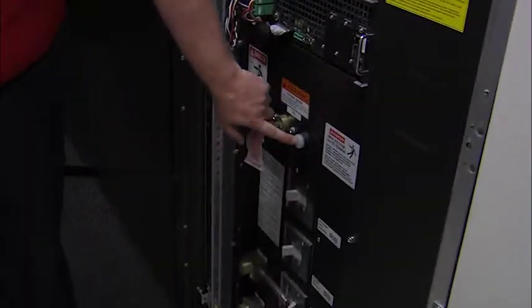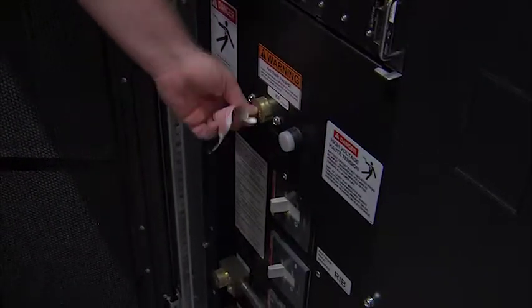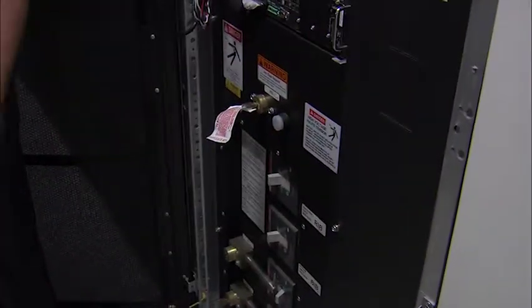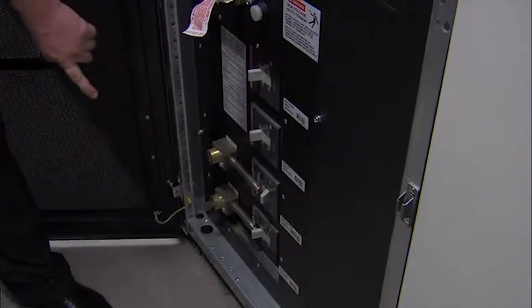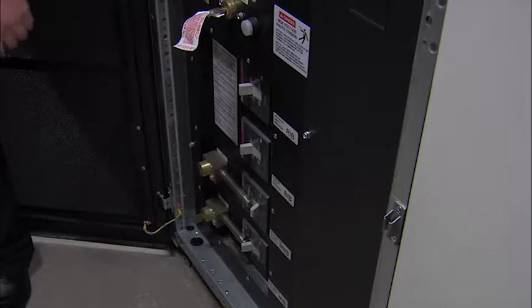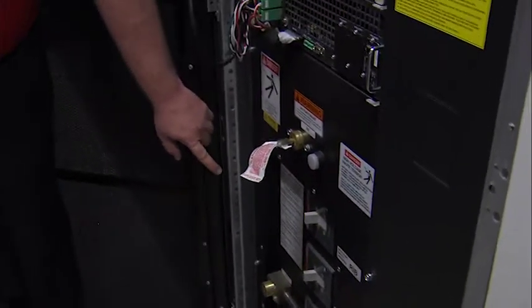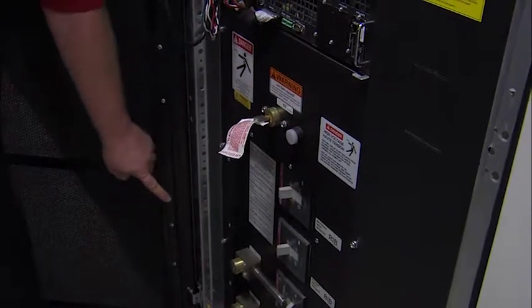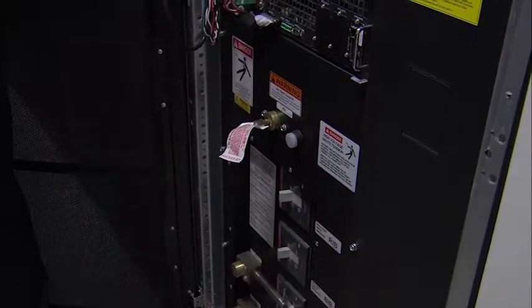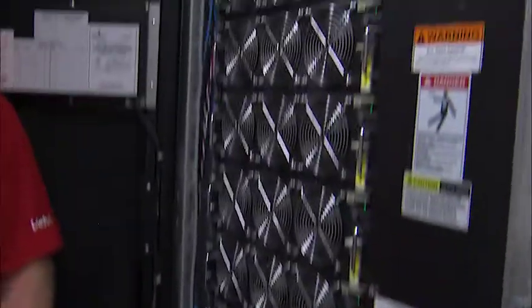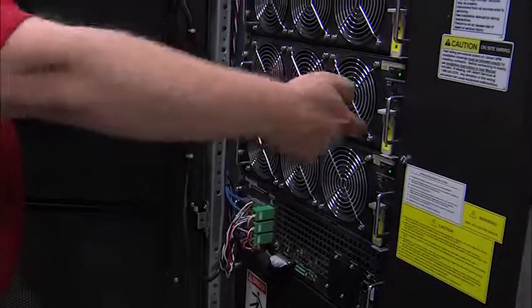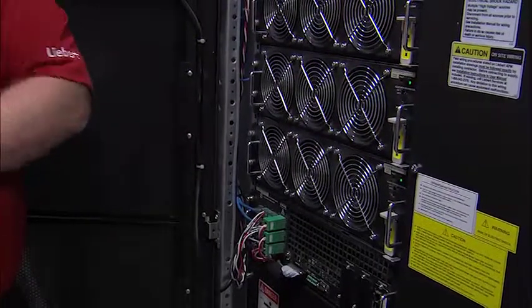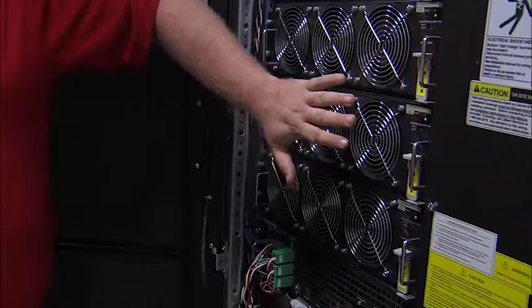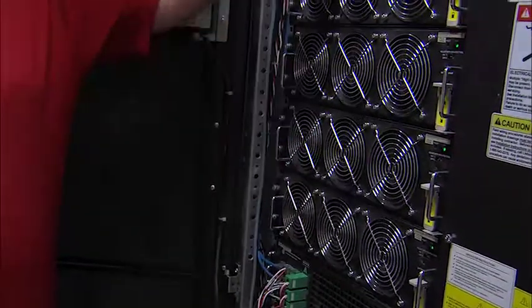At that point, this light will light up. This is a solenoid, so you cannot turn this key until that light lights up and you push that button. Once that's done, you pull that key out and put it in there, and then you can close that breaker and open that breaker. Let me correct that: you close that breaker and open that breaker. At that point, your load is now not on any of these modules. So they can come in here, flip the switch, unscrew it, and pull this module out. This is the whole inverter module itself, which you have redundancy built in.